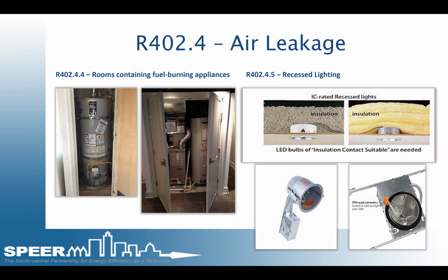So combustion air and exhaust air must be brought into the space, providing the appliance with combustion air and venting the byproducts outside the envelope. With this, you should see two metal pipes in the ceiling. One is long enough to almost reach the floor of that room or the platform that a water heater is sitting on. The other will be much shorter and just barely coming through the ceiling. That's a high-low pipe that has incoming air coming in from the outside and exhaust air, or byproducts, leaving through the one at the top.